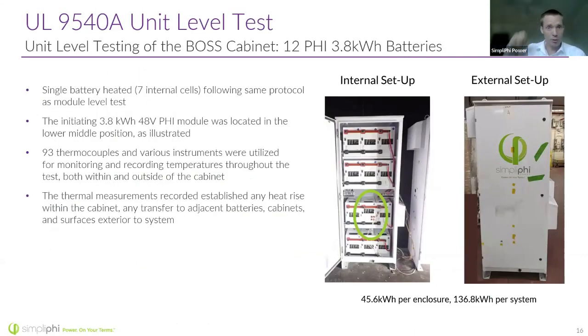The unit level test is where we take a bunch of batteries, a bunch of battery modules, and we put them in close proximity, how they might end up being placed in the field. So what you can see here, this is a BOSS 12 enclosure being tested. We're testing a 136.8 kilowatt hour battery system, which includes 3 of these battery cabinets side by side in the testing setup. So again, we're going to take an individual battery, we're going to force it into thermal runaway, and we're going to see how the other batteries around it respond.